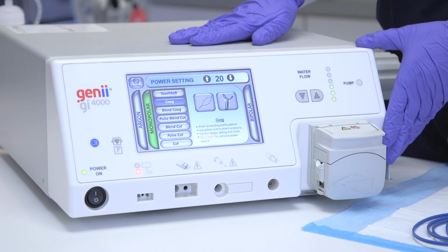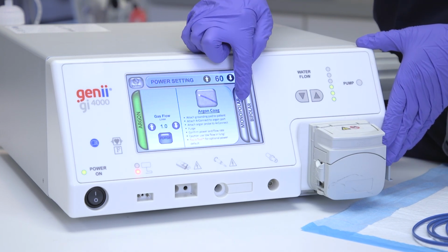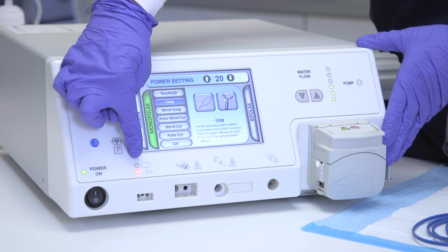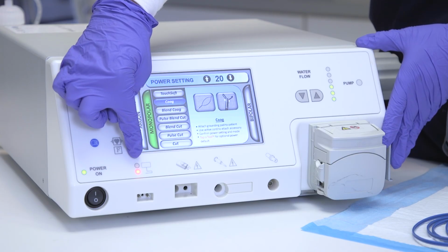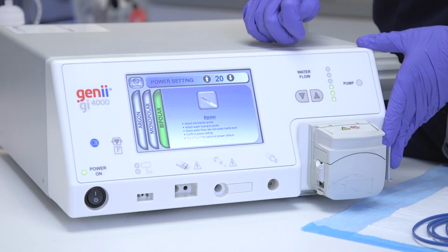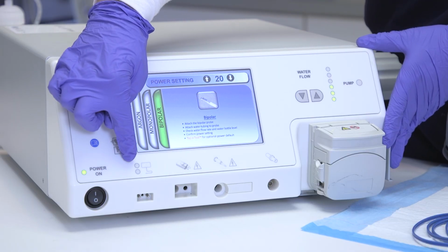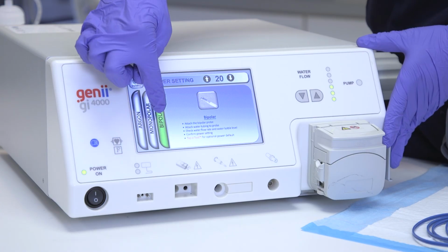Let's talk about grounding pads. Both Argon and Monopolar require a grounding pad. You'll notice that we don't have a grounding pad plugged in, so the light remains red. When you tap to Bipolar, the grounding pad light goes away. It's a good indication that you don't need to have a grounding pad applied for Bipolar.